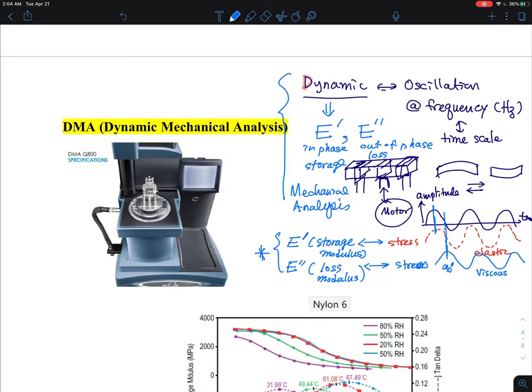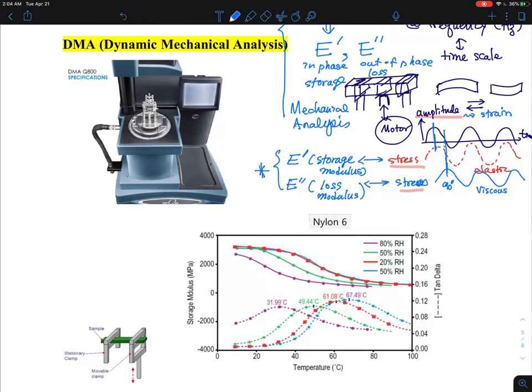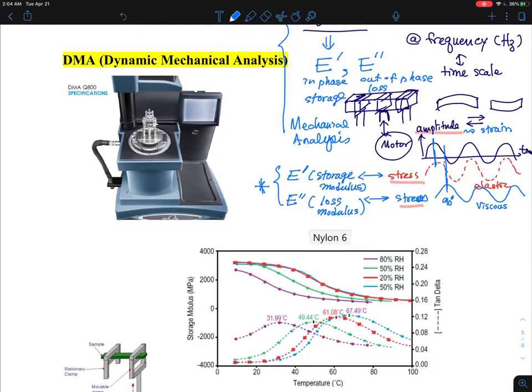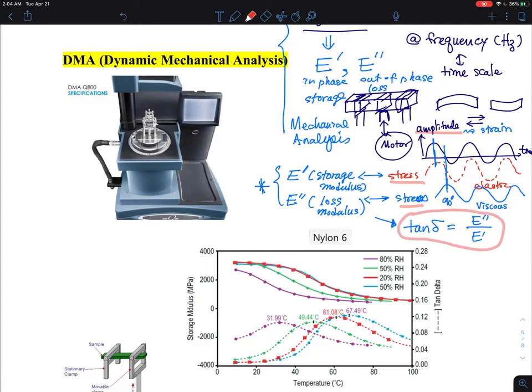You are moving the sample in and out, measuring the deformation — called the amplitude — and measuring the stress. The relationship between strain and stress allows you to find the storage modulus and loss modulus. People are also interested in measuring the glass transition temperature, and they use tan delta, which is E double prime divided by E prime, looking for a peak in tan delta as a measure of Tg.